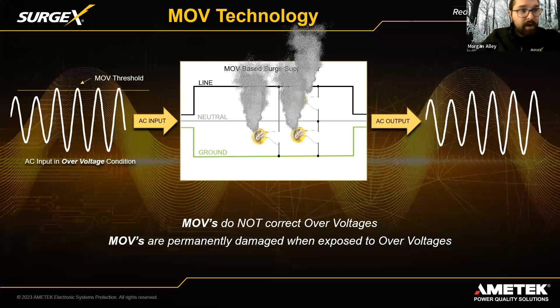You will see in some manufacturers, their MOV-based products will have an indicator where, say, if it's functioning right, you've got a green light, and when the MOVs burn out, it'll switch to a little red light, or maybe it'll make a humming noise. That's the best-case scenario, but in the majority of products on the market, they're not even going to tell you when those MOVs are burned out. So oftentimes you'll literally just have a surge protector that you've been using for years, and it's completely doing absolutely nothing other than distributing power across a couple more outlets for you. So that's what we are up against and what we're differentiating ourselves against.